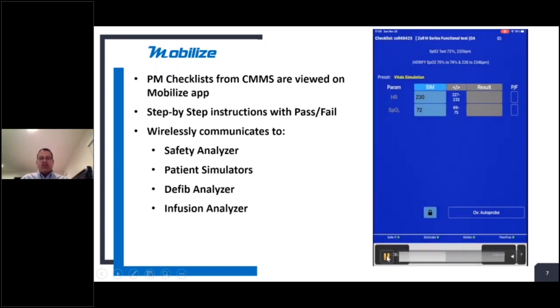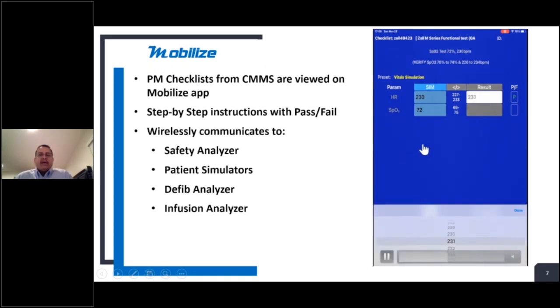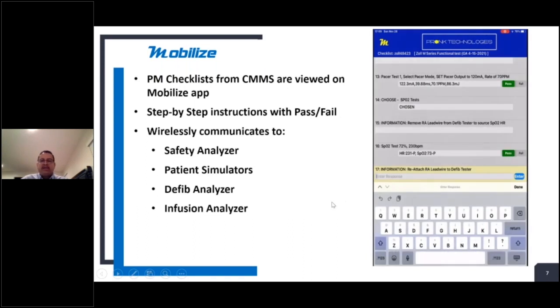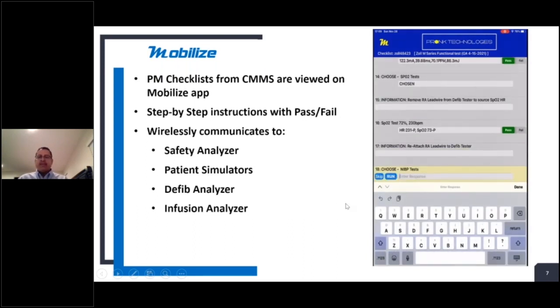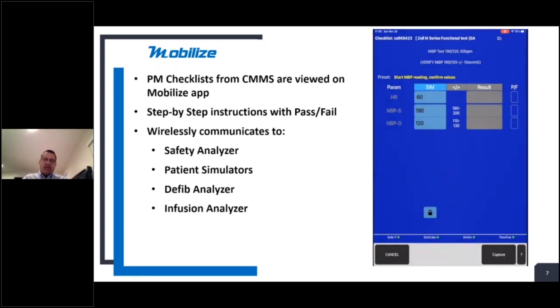Now, if you have other devices or other tests, in this case, I need to also do an SpO2 test. So you can see at the top here, it says, let's run an SpO2 test at this particular pulse rate. You have the values here that have automatically been sent to the simulator saying set those values. And here, if you'd like, you can also program pass-fail tolerances. So based on the result that's captured, the application would automatically tell you whether that result is within range or out of range. And so I could do this for a wide range of products. More instructions here on what to do in terms of the setup of the analyzer. If you need to do other tests for different parameters, you can have all those done separately. You can combine them into one step, so you don't have to do them serially. Up to you. This particular procedure wants a technician to do them one step at a time, and so that's why you see it laid out this way.